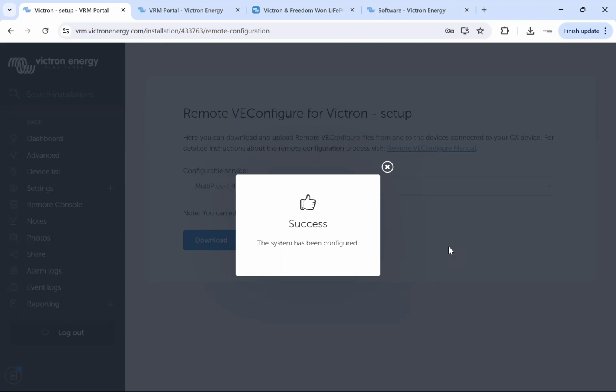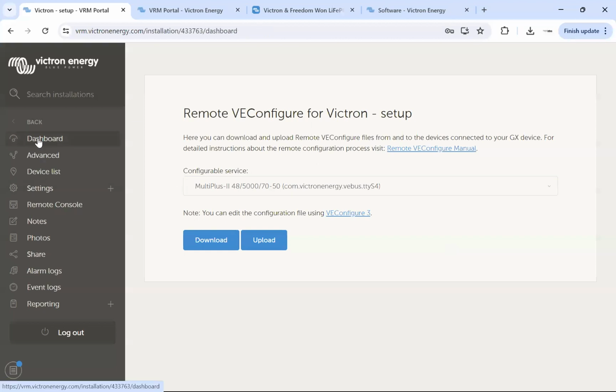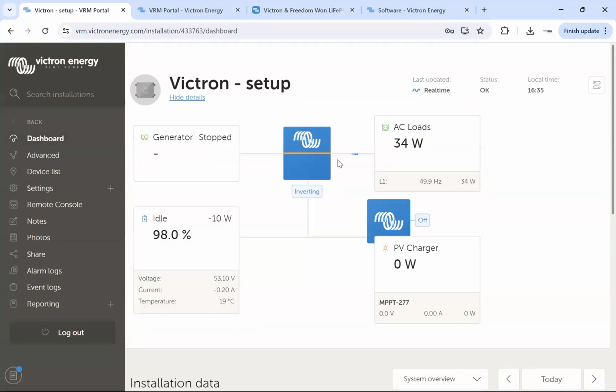But there we go, it's been configured. Now I'm going to go to the dashboard and have a look. We can see AC loads of 34 watts, about 7 watts of that is just the inverter's own load. We've got nothing happening on PV because there's no PV attached, no amps and no voltage. And we've got negative 10 watts coming out of the battery, which is just enough to keep the inverter idling along.